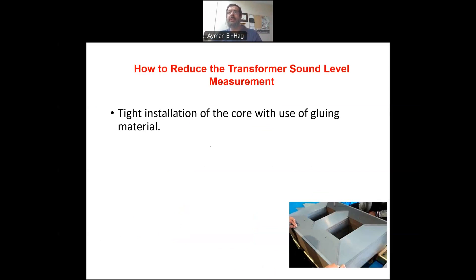Sometimes you do that using automatic setups but most of the time you do that using some skilled workers. So you have to make sure that there is no air gaps here and you try to make the design as tight as possible. Also you add glue once you are done with the stacking of the sheets. You add glue all over the place to hold those core sheets and minimize the vibration effect. You cannot completely remove the noise but you can try to minimize that.